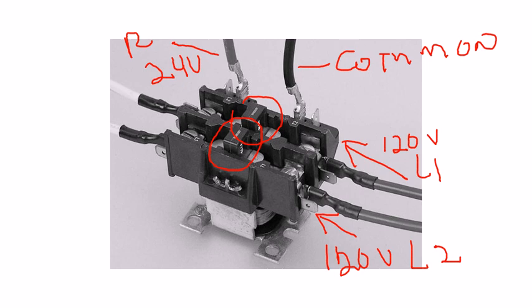That 24 volts going to this coil down here will suck these contacts closed, just like turning a light switch on, and when that happens we're going to take the 220 volts out this side and supply the compressor and the condenser fan motor.